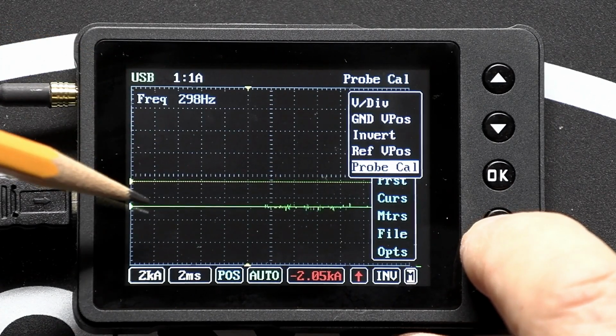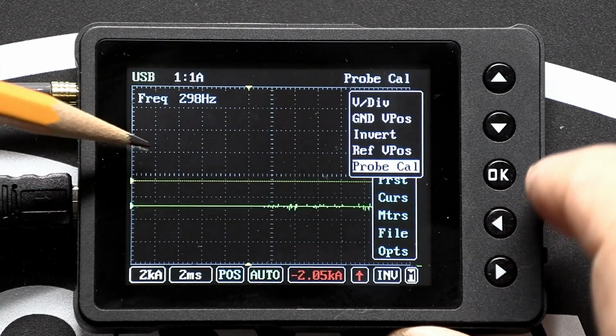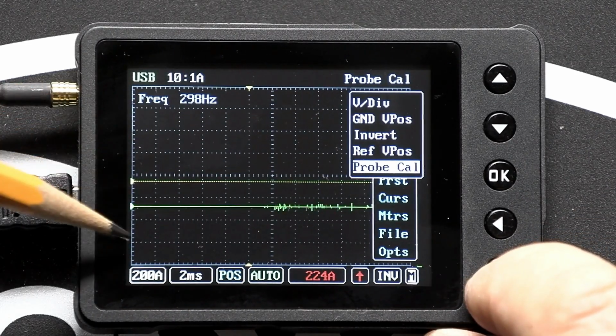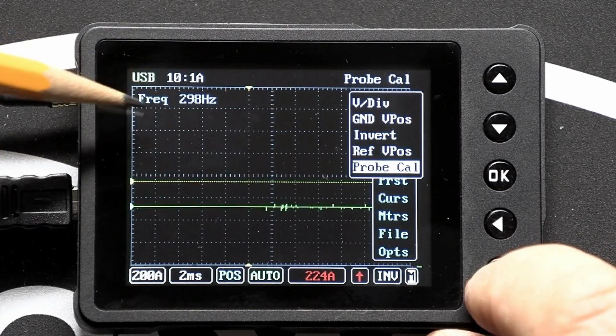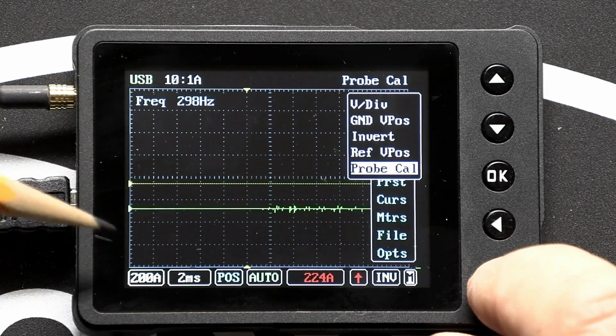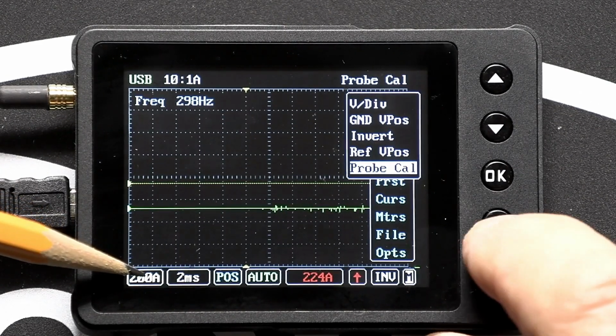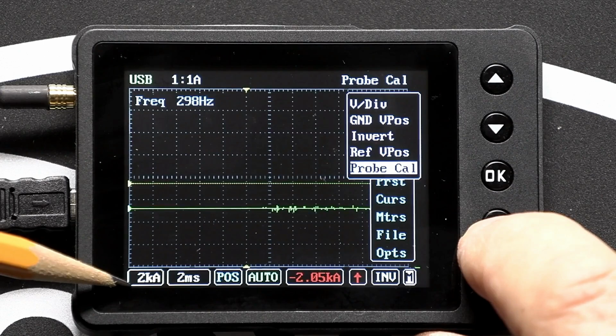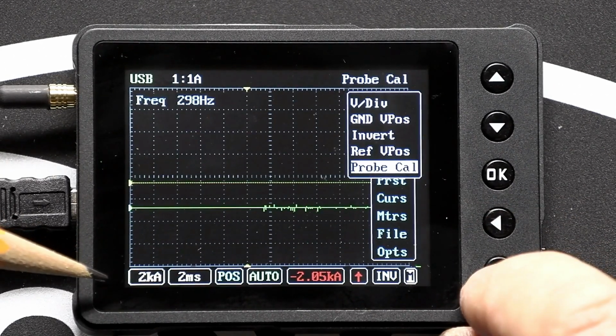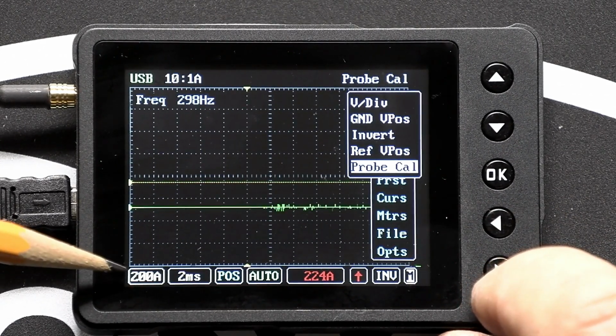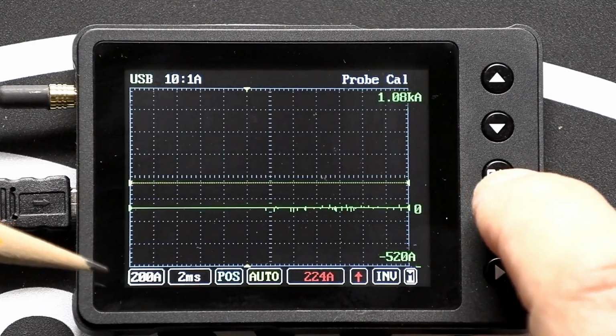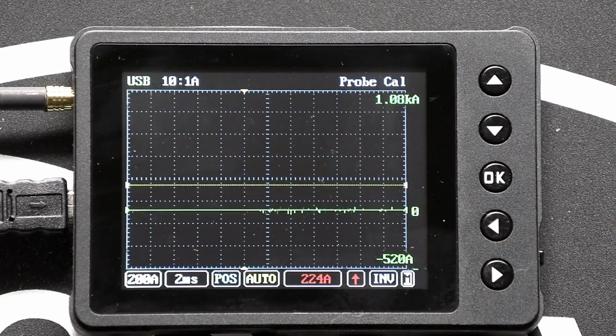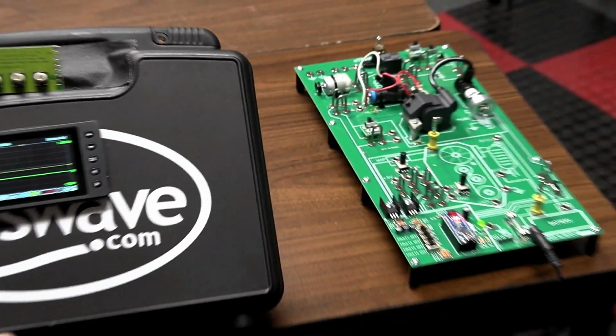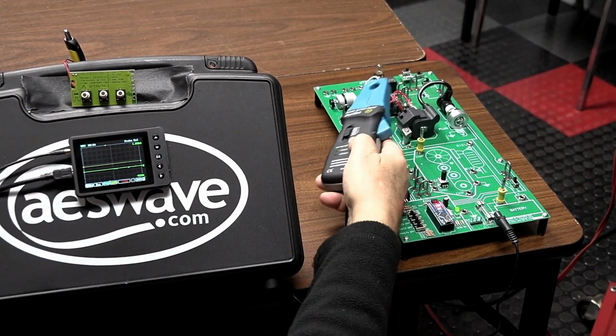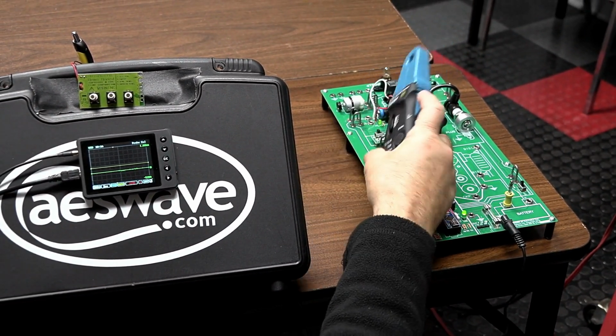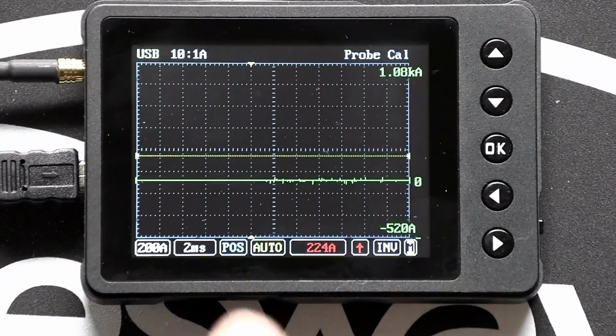If that doesn't work real well, let's see something if I went back one. We're going to use the 10-to-1. Why? Because it puts me on a 200 amp scale rather than on a 2 kA scale. So we're going to put that right here, I'm going to hit OK, go back to the test board, put it on. I'm going to take my amp clamp, zero it, too high of a scale.